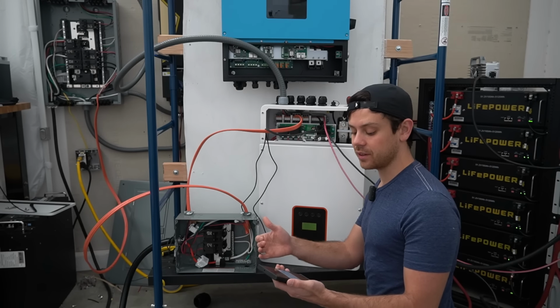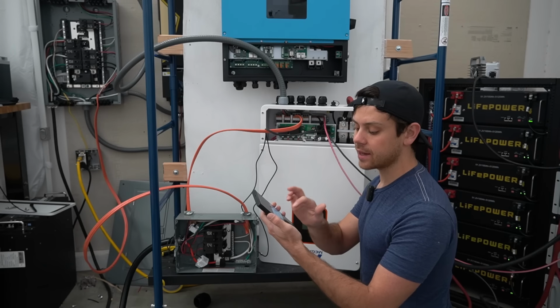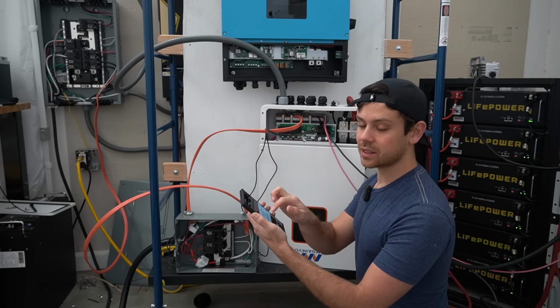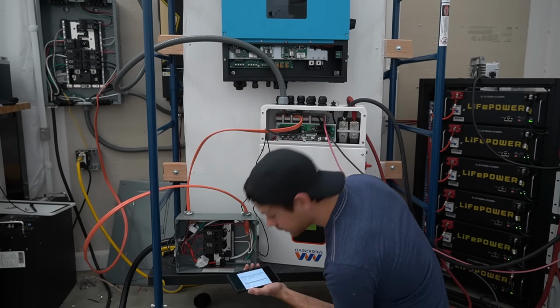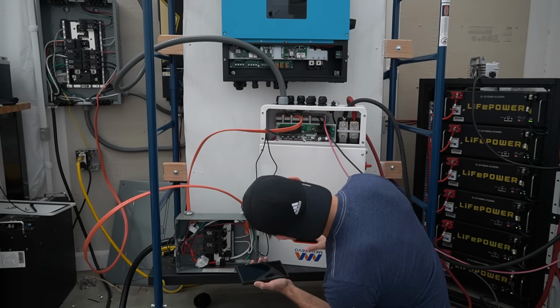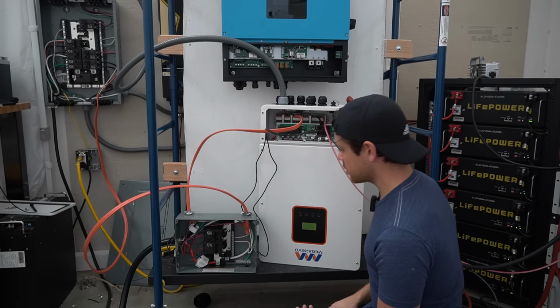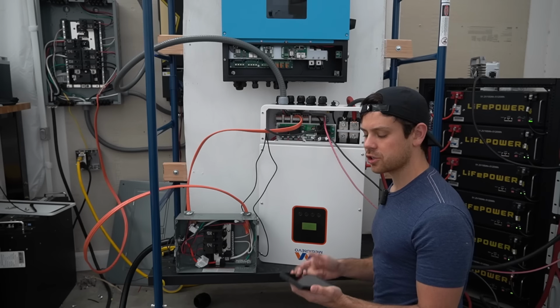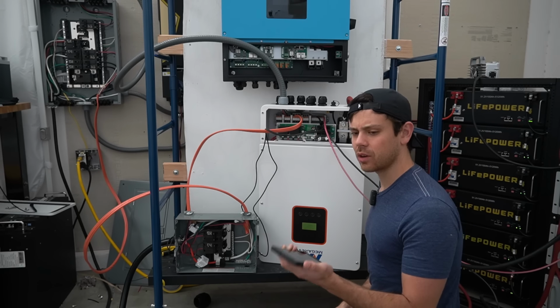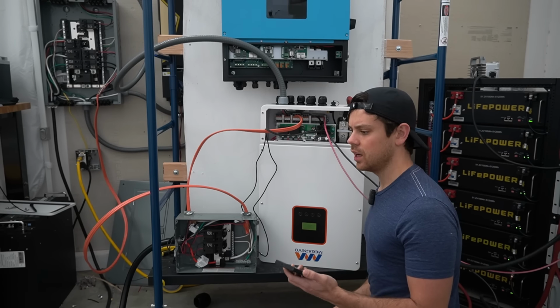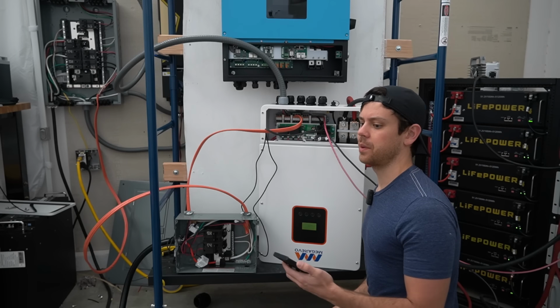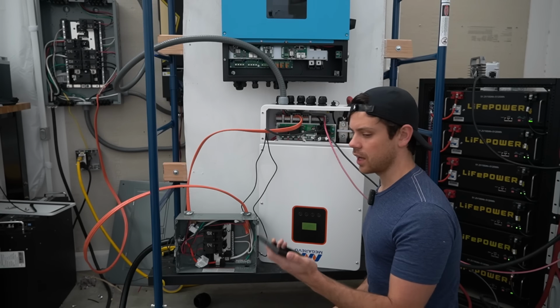Now to make this system work and to run our loads off of the grid and solar without backfeeding the grid, we need to change the anti-reverse setting. And it comes disabled, but we need to enable it. And it's under System Settings. Oh, it's enabled. That's strange. If you buy it from Signature Solar, it should come disabled. So yeah, I would recommend everybody actually check that setting to see what it's at, because you do not want to backfeed the grid on accident. So yeah, check that setting.